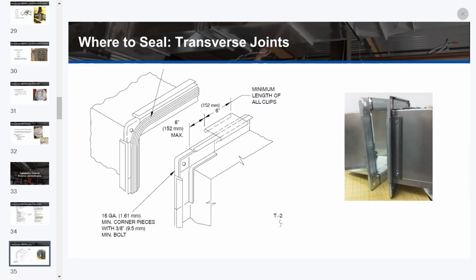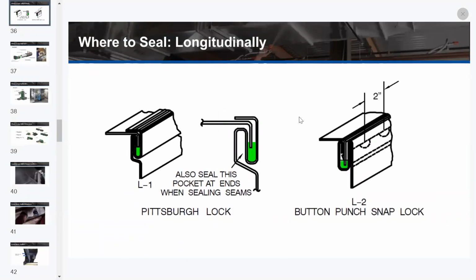If you're putting the transverse joints together on the job site, make sure you take that butyl gasket or that EPDM gasket, whichever you're using, and loop that in the corner. That can help seal that and make your sealing after that much easier. Longitudinally, typically a Pittsburgh lock or a snap lock should have a sealant, shown here in the green, in the pocket, which then seals the longitudinal seam once it is snapped together. Now that doesn't mean the longitudinal seam is fully sealed, as at the end of the duct section it is straight cut, and that can allow an air pathway where you can see leakage along the longitudinal, right, as air is always looking for the path of least resistance.